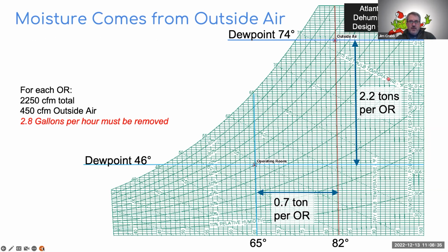And so if we try to take that outside air down to the condition we want in an operating room, 46 degree dew point at 65 degrees, you can see we're going down the chart and to the left on the chart. Left to right is sensible heat, and up and down is moisture. And you can see there's a lot more moisture involved, moisture that needs to be removed from that outside air to get to an operating room design condition. That's much more significant than the sensible heat that needs to be removed. Next slide.